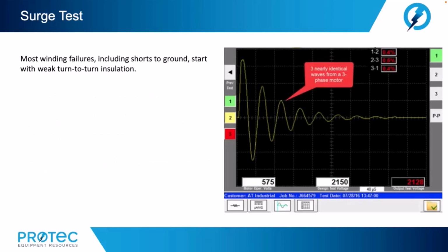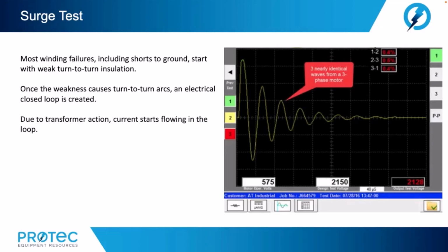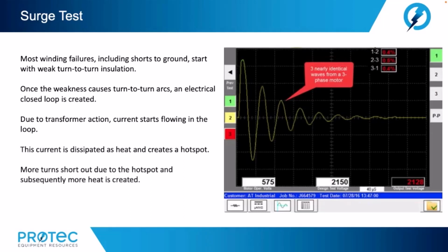Most winding failures, including shorts to ground, start with weak turn-to-turn insulation. Once the weakness causes turn-to-turn arcs, an electrical closed loop is created. Due to the transformer action, current starts flowing in the loop. This current is dissipated as heat and creates a hot spot. More turns short out due to the hot spot and subsequently more heat is created. Eventually the winding shorts to ground.